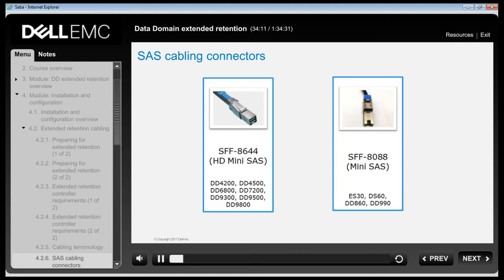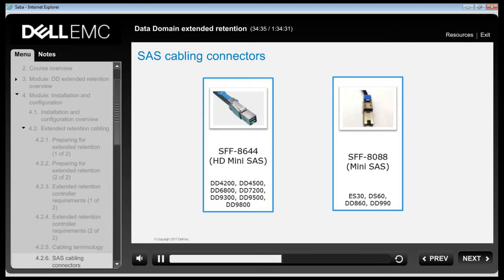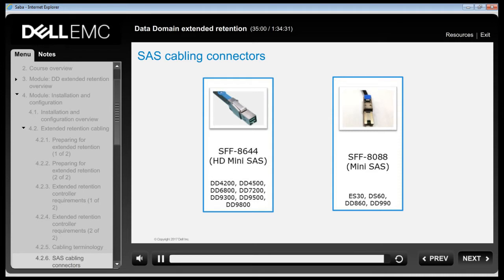The Data Domain system supports two types of SAS cable connectors: SFF-8644 and SFF-8088. The SFF-8644 connector, also known as HD Mini SAS, is required by newer Data Domain controllers including the DD4200, DD4500, DD6800, DD7200, DD9300, DD9500 and DD9800. The SFF-8088 connector, also called Mini SAS, is required by the ES30 and DS60 expansion shelves, and also by DD860 and DD990 controllers.